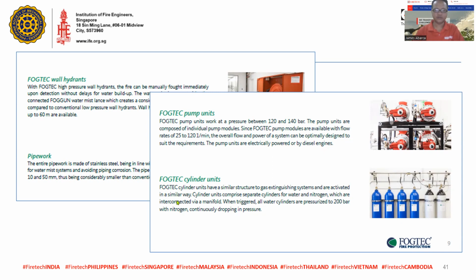There are also FOGTEC cylinder units. Cylinder units have a similar structure to a gas extinguishing system, almost the same, but cylinder units comprise separate cylinders for water and nitrogen, which are interconnected via a manifold. When triggered, all water cylinders are pressurized to 200 bar with nitrogen, continuously dropping in pressure.